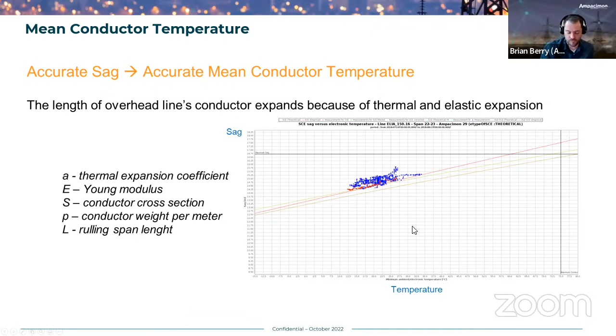So as I mentioned here, sag comes in, and using all of these lovely coefficients, which I'm not going to talk about, I can convert sag to temperature, and we can measure sag from these vibrations down to 20 centimeters worth of error. And we can get a very good measurement of the temperature of the line.